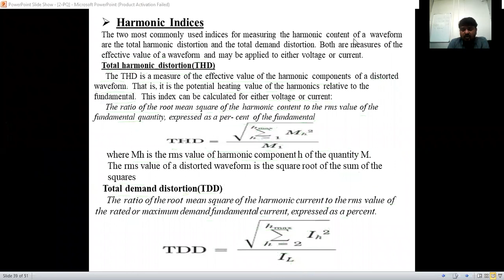The next part is called interharmonics. Interharmonics are nothing but a non-integer multiple, not an integer number, of the frequency. Normally harmonics means a multiple of integer numbers, but interharmonics are not integer multiples.